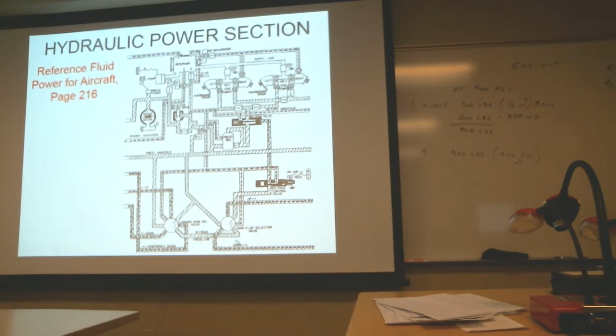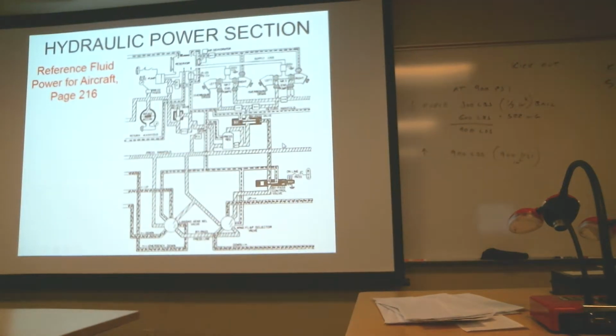Anything else, the selector valves are kind of strange. They use a combination of open center and closed center selector valves in the circuit for operation of the equipment that's downstream. But this is what we have, at least for the power side of the circuit. Oh, also notice too, check valves. For isolation of an inoperative pump via maybe a broken shear shaft, they use check valves to prevent motoring of the inoperative pump. So that's kind of common on many of the multiple pump designs that feed into a common manifold for discharge.